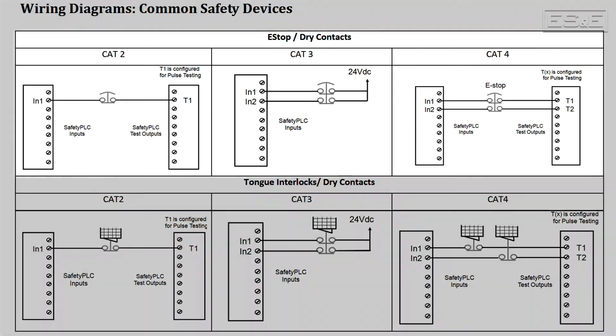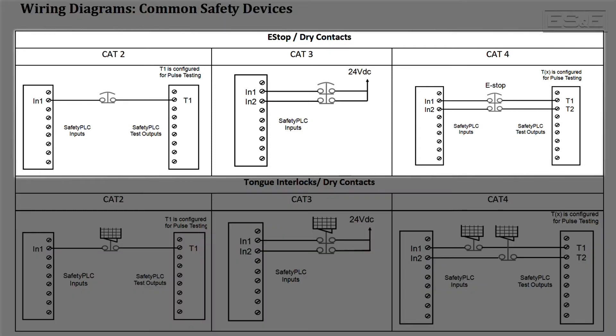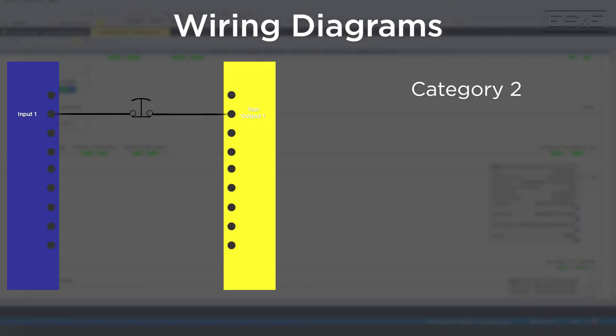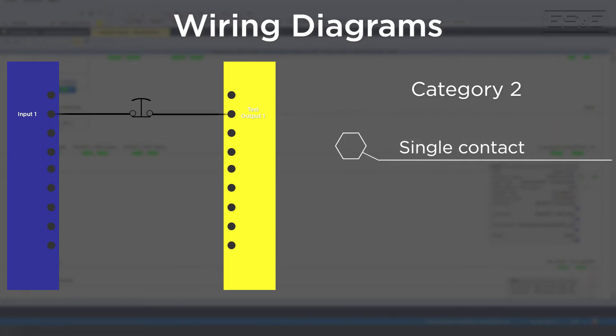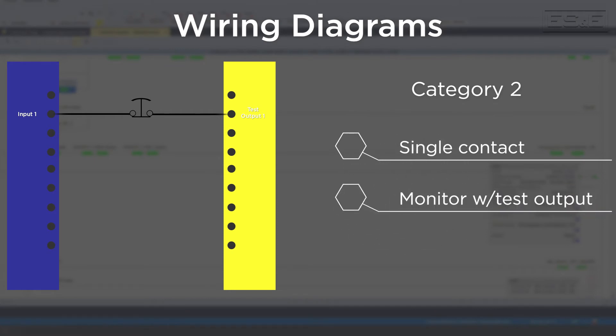In our example, we will review a simple e-stop pushbutton circuit and the first category will be a Cat 2. For a Cat 2 circuit, you only need to have a single contact, but you must monitor the contact with the utilization of a test output from the safety I/O card.